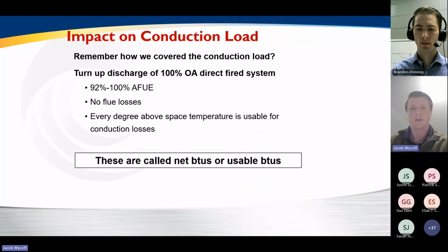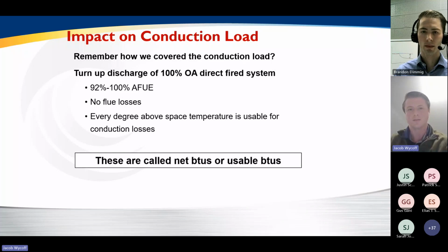Now, remember how Brandon talked earlier about separating the conduction load and the air load, and about how every degree we turn the discharge of our 100% outside air direct fire system above the space temperature, we get BTUs that are usable to cover those conduction losses, which is our heat losses through the walls and the roof, through the skin of the building. And for a lot of these applications, that's primarily what we're concerned about. We're not concerned with over-ventilating the space, especially for spaces and buildings without a lot of process exhaust, without a lot of occupants in there. We really just want to be able to heat the space.